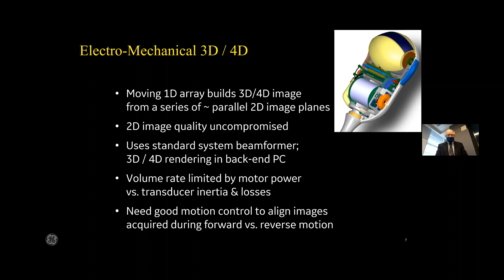as it says here, with certain difficulties with actually making this thing wobble back and forth in a stable way. In particular, you need an awful lot of good motion control to align images. The other thing that's not necessarily obvious is that you typically have a shell over this thing. You don't want the wobbling thing on your surface. And that tends to be a place where you end up having all sorts of inner artifacts come about.